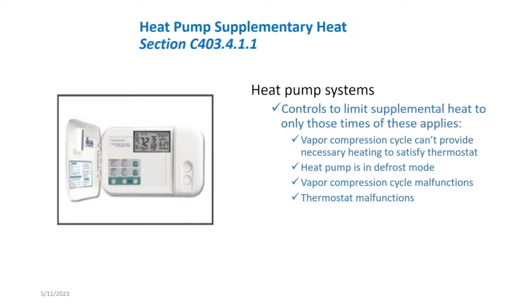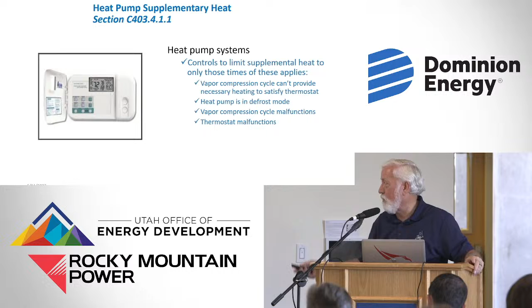Basically, heat pumps, I think everybody understands, a heat pump in the wintertime pulls heat from the cooler outside, brings it inside, or if it's a ground source, we pull it out of the ground, bring it inside, and it reverse cycles in the summertime. Well, in the wintertime, if it gets really cold, we might have a heat pump that can't keep up because we're trying to pull heat out of an already cold environment. Does that make sense? And so some heat pumps will have a supplementary heat. And if it's electric heat, which is basically big toaster strips, we don't want those on unless we absolutely have to. So what this requirement says is if the heat pump through refrigeration can keep up with the load, the strips have to be locked out so that we can't be wasteful in our energy usage. Again, this is one that I could meet with you more after.